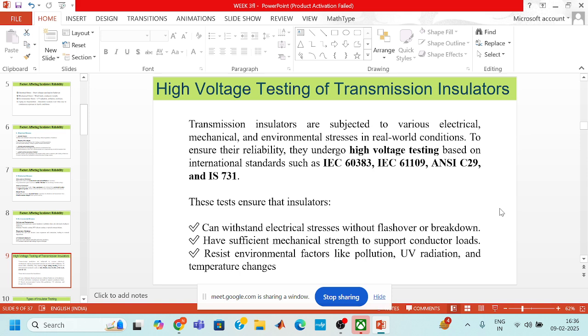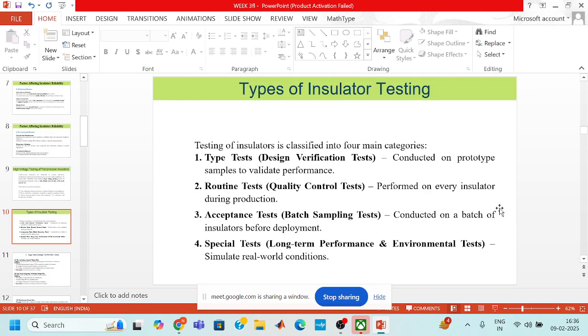Why are we doing testing? Because by testing, we ensure the insulators can withstand electrical stresses without flashover or breakdown, have sufficient mechanical strength to support the conductor loads, and resist environmental factors like pollution, UV radiation, and temperature changes. Basically, there are four types of tests: type test, routine test, acceptance test, and special test. The type test is used for design verification, also known as design verification test. It is conducted on prototype samples to validate performance.